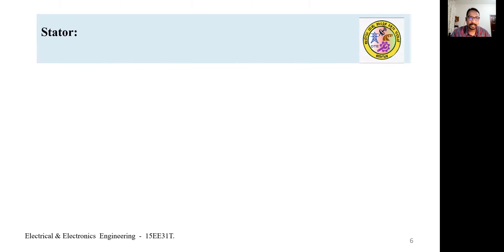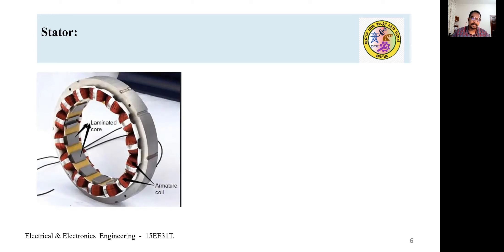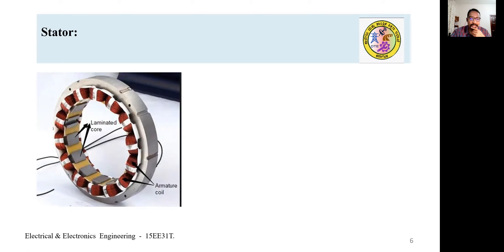The stator, as the name implies, is the stationary part of the alternator — which is the armature containing the conductors. On the inner periphery of the stator, slots are provided. This inner periphery is made up of thin laminations of silicon steel. Silicon steel is used because it has very low hysteresis loss, and the thin laminated sheets reduce loss due to eddy currents.